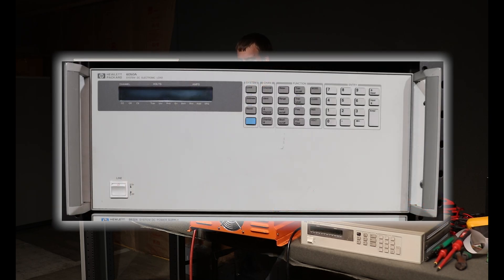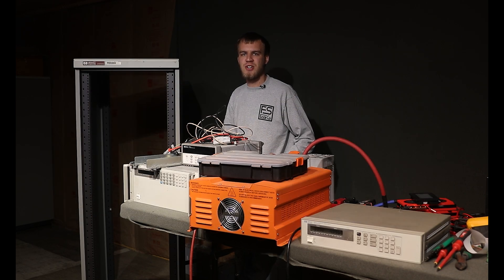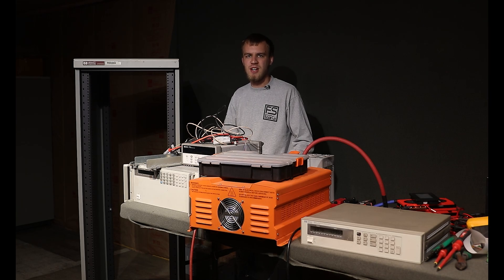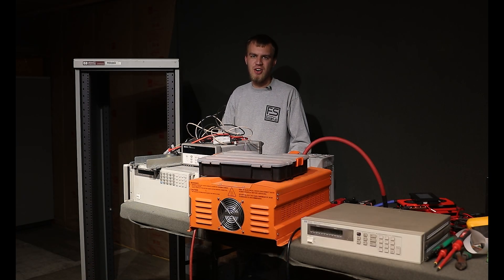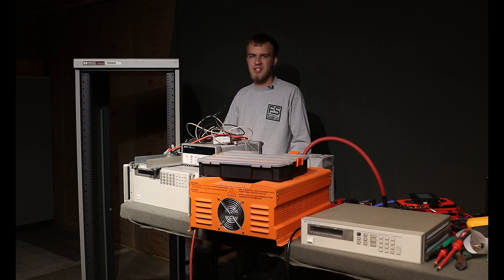So this electronic load, we'll get in a little bit more detail here, but essentially this will turn 1800 watts of electrical energy into heat and we can use that for testing batteries at constant voltage, constant current, constant resistance, and constant power. A real versatile unit for many tests here in the lab.